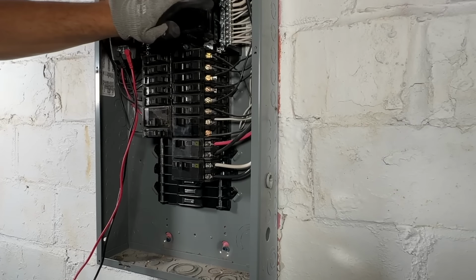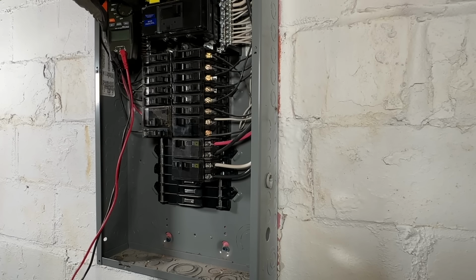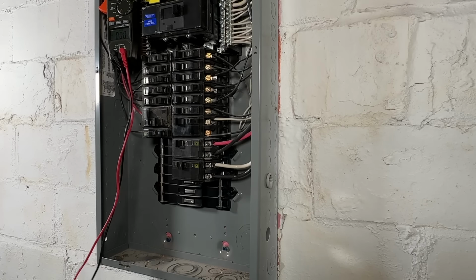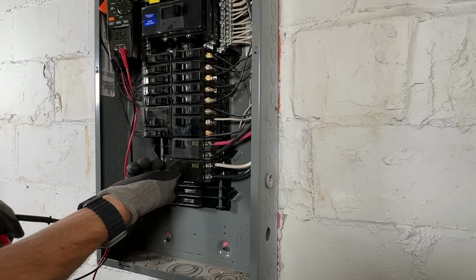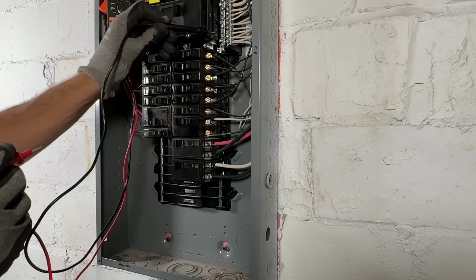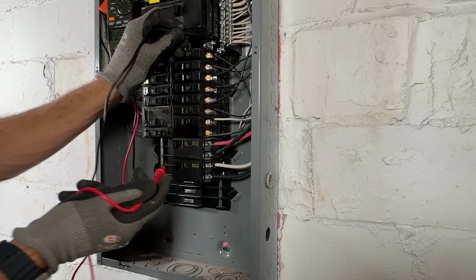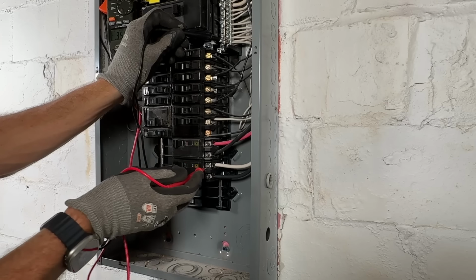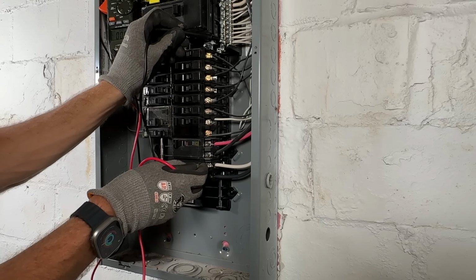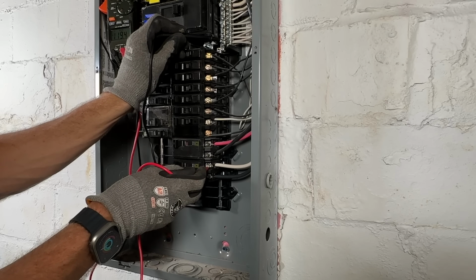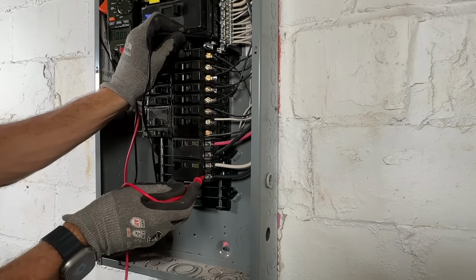So now everything is wired up, and then let's test our work. I'll move my clamp meter so we can get the multimeter functionality. Then we'll go ahead and turn on our breaker. Black probe goes to the neutral, which is actually grounded at the main panel. Then we'll test this, getting 119.4. So our first phase looks good.